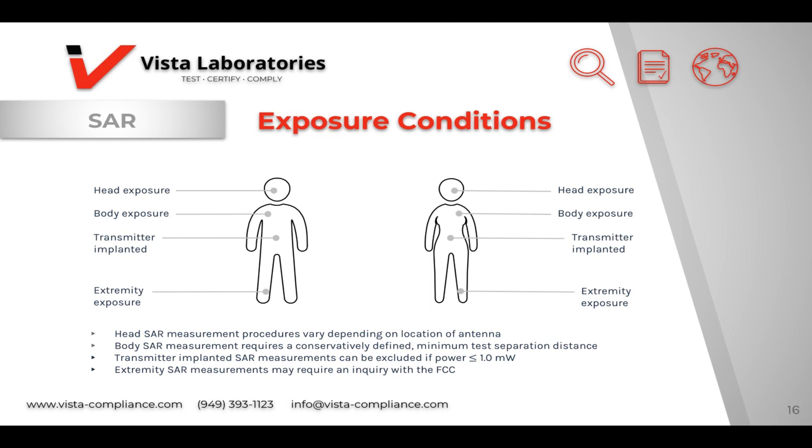So all body-worn accessories must be disclosed to the user through the user guide or manual. Unsupported accessories are not used. This ensures that the device as a whole would still comply with RF exposure limits.